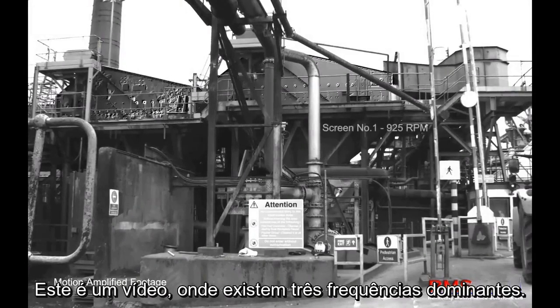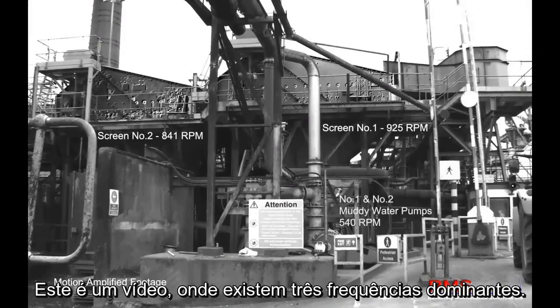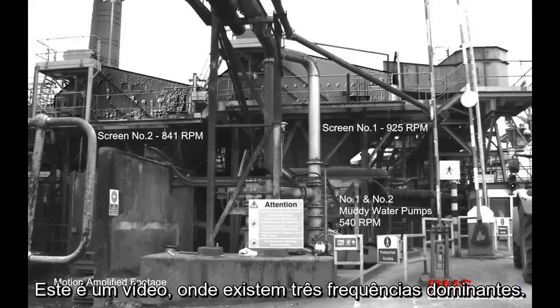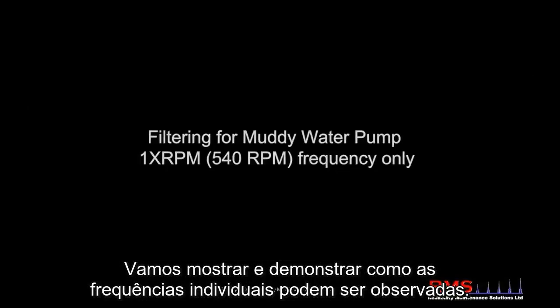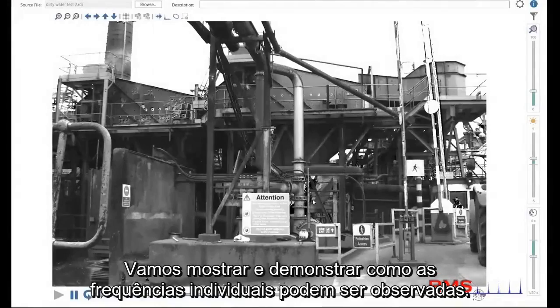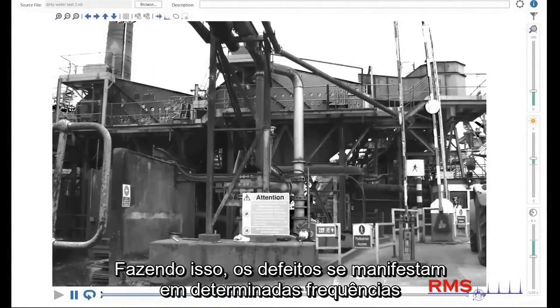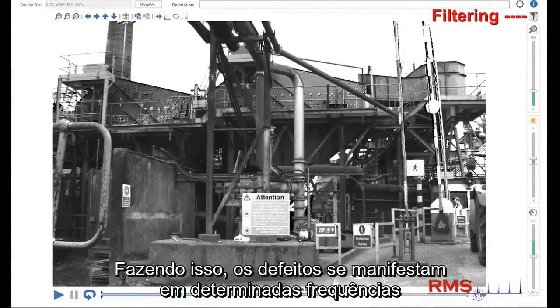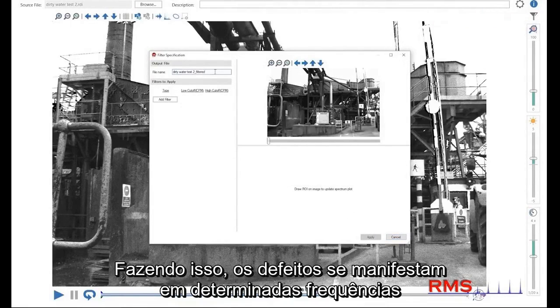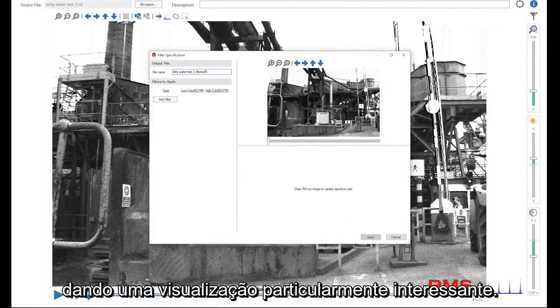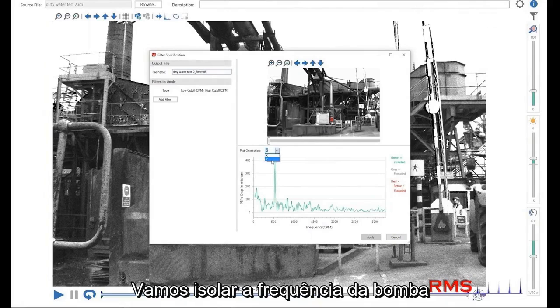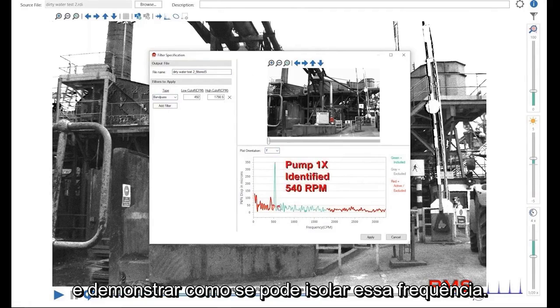that here. This is a video where there are 3 dominant frequencies in the video, and we're going to go through and just demonstrate how with this you can look at individual frequencies, right? And when you do that, faults manifest at particular frequencies, so it gives you a particular interesting look at it. So here we're going to isolate that one frequency on the pump, and demonstrate how you can isolate that one frequency.